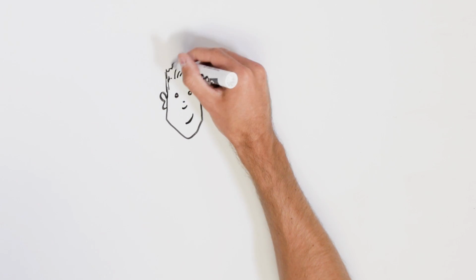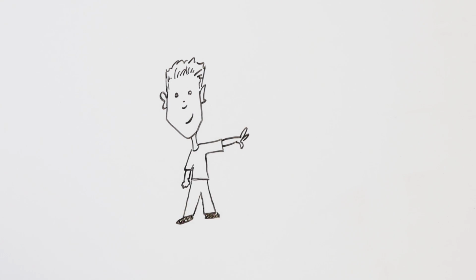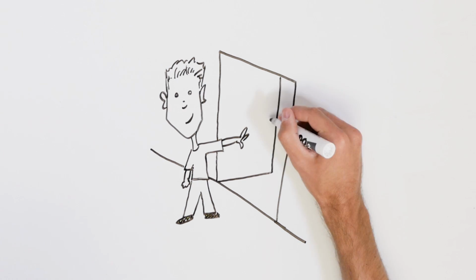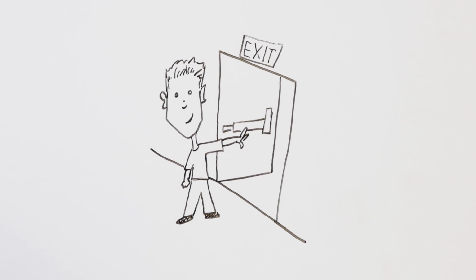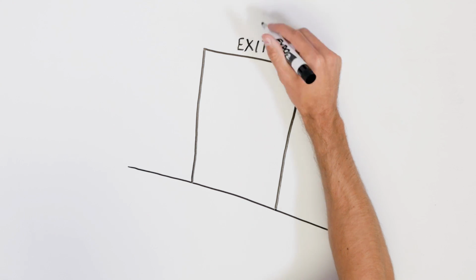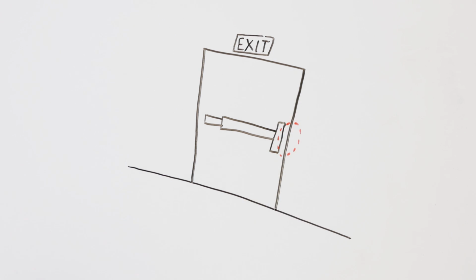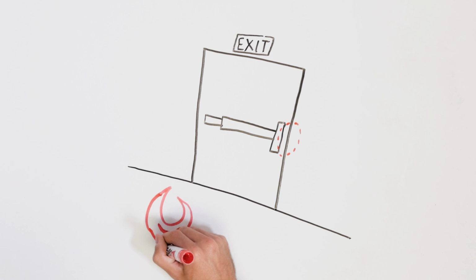A few important things to note. First, these locks on stairwell doors are on the stair side of the door, except for the stair discharge door. With the exception of controlled egress locks in healthcare facilities, locks in detention and correctional facilities, and delayed egress locks, free egress from the building to the stairwell is almost always required. Second, because most stairwell doors are fire rated, the doors must remain latched even when they are unlocked by the Fire Command Center or the fire alarm system. The positive latching ensures that the fire doors will be closed and latched against the pressure caused by a fire. Fail-safe electric strikes may not be used in stairwells because they are not listed for use on fire door assemblies.